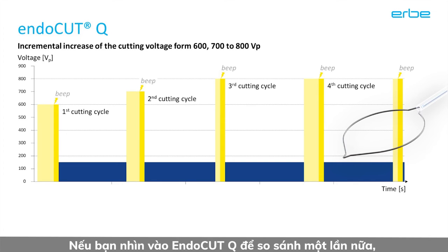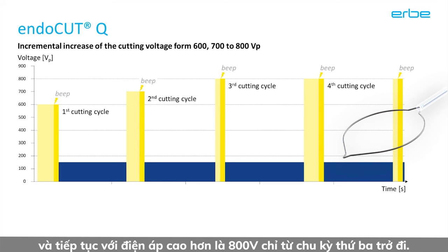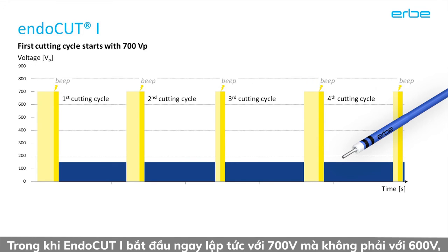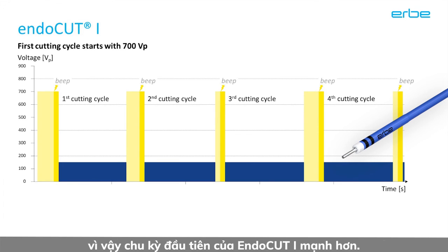If you look at the EndoCut Q for comparison once again, the difference in voltage becomes noticeable. EndoCut Q starts with 600 volts and continues with the higher 800 volts only from the third cycle onwards, whereas EndoCut I starts immediately with 700 volts and not with 600 volts. So the first cycle is slightly stronger, but the later ones are a bit lower than with the EndoCut Q.